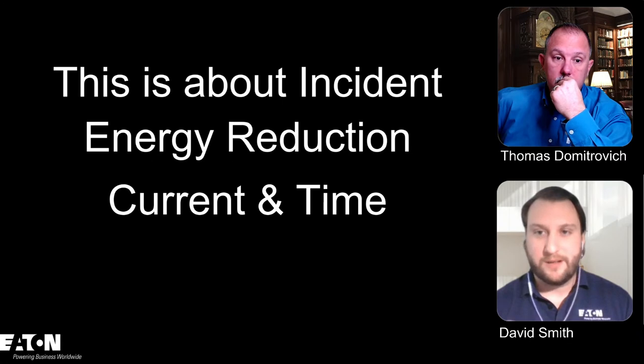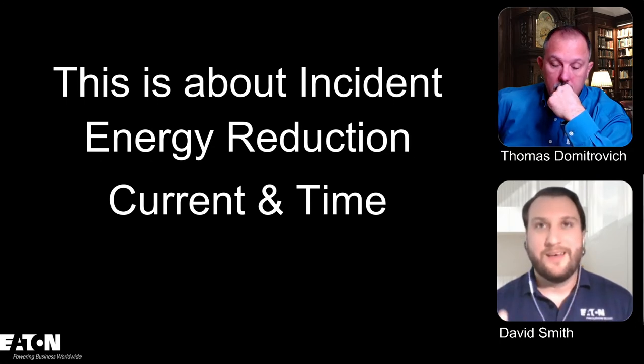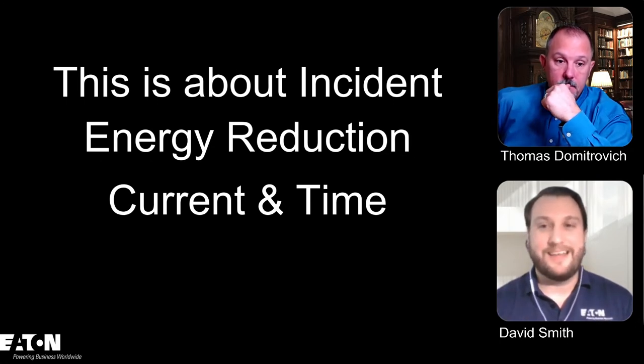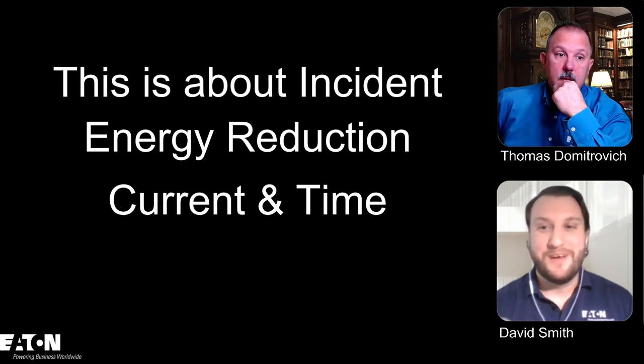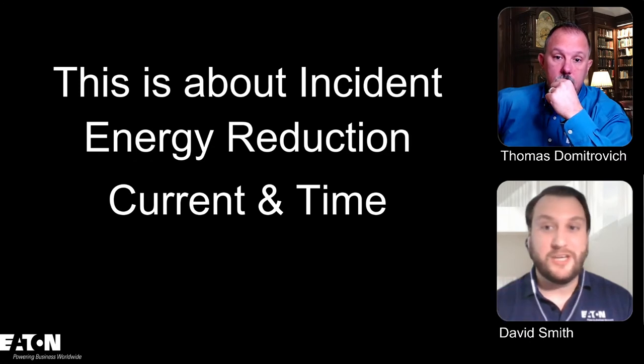However, whenever we're talking about clearing time and maximum arcing current and minimum arcing current, which we will get into later, maximum arcing current, everyone likes to talk about because that's maximum, right? It's sexier. But the minimum arcing current is really what we're talking about today, because it can be just as dangerous as maximum. It can be just as deadly. And so we are really talking about the clearing time of the minimum arcing current.